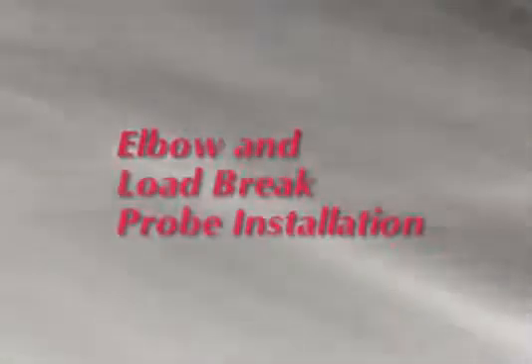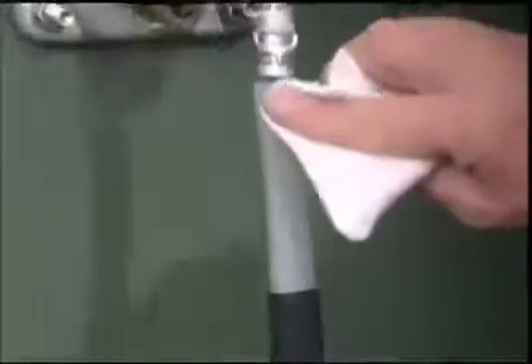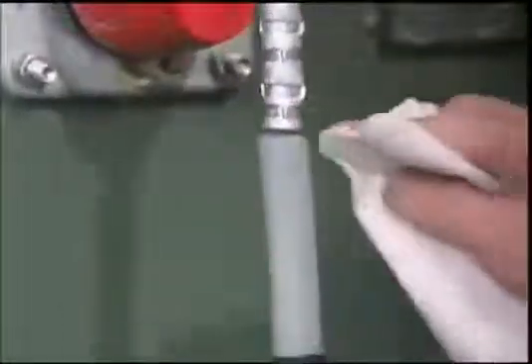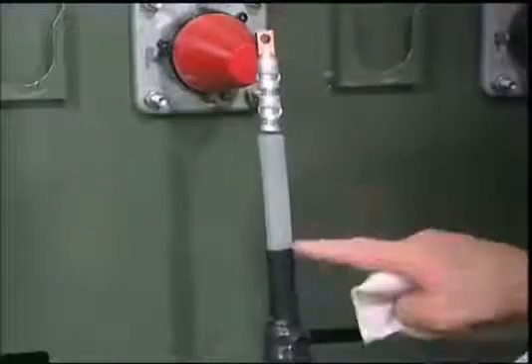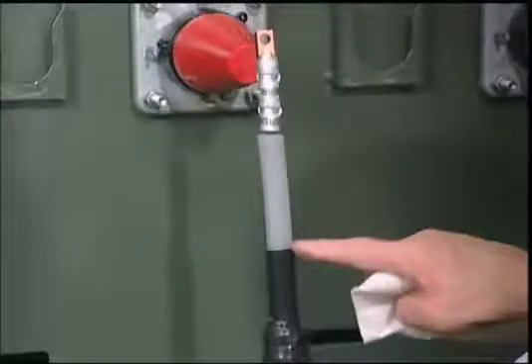Elbow and load break probe installation. Next, clean the insulation with a customer-supplied lint-free cloth saturated with cleaning solution. Do not apply the cleaning solution directly to the cable. Start at the top and wipe away from the crimp connector, and do not touch the black insulating shield.